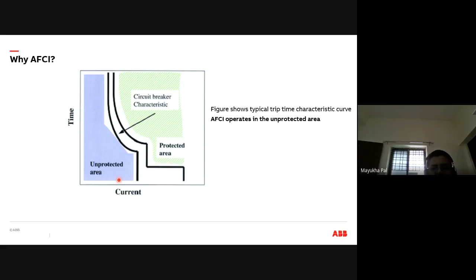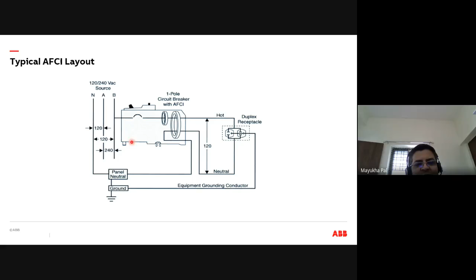Typically, how an AFCI for a residential application looks: you have your line and the neutral, and this is your device. You have your sensors that sense the typical arc current, and this is where your load is. This device is a single pole device, by the way. So this is how a typical arc fault circuit looks for residential applications. In the US, every house needs to have an arc fault and a ground fault device mandatorily. And house in the sense every room. It's mandatory to have an AFCI and a GFCI in every room. That's not the case in India, but that's the case in most Western countries. That's essential.